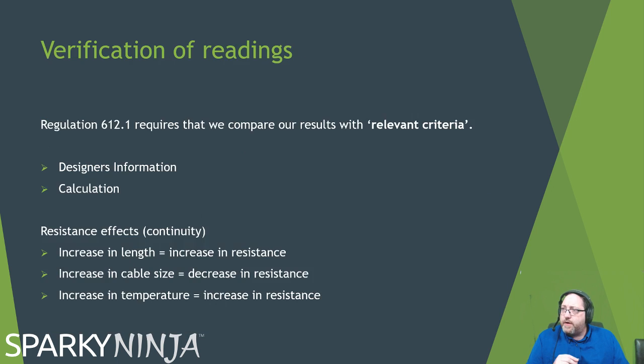What you need to know though is what the reading should be. If I'm going to go to a socket and go, there's a number, is that number any good? Do I know what it should be? If it's an initial verification, I should have some designer information. It might tell me what the measurement should be, and I'll go, great. If I haven't, I might need to collect some other information and understand how to calculate it myself.